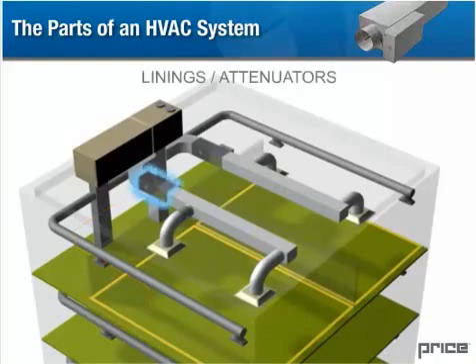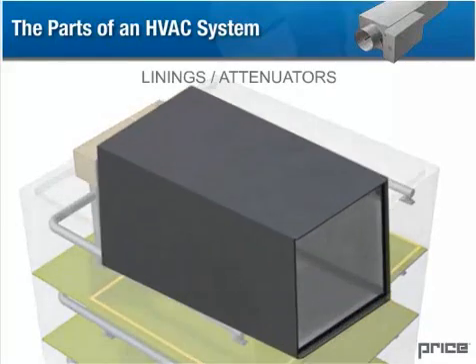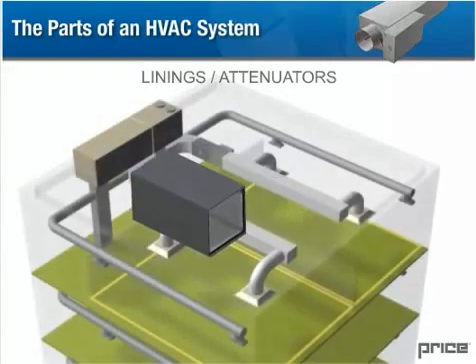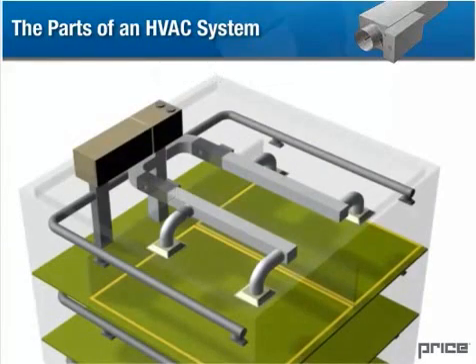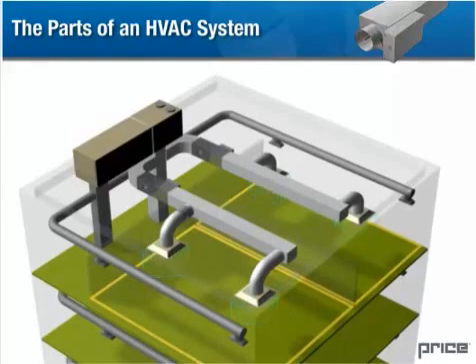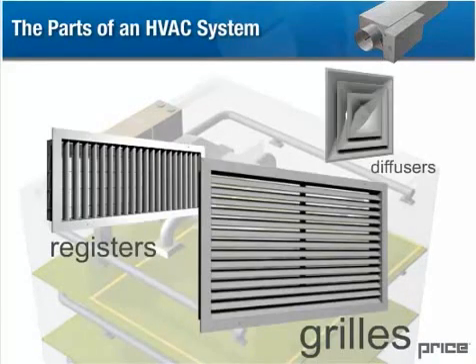Various types of linings are available to dampen noise within a duct. A short length of lined ductwork, called an attenuator, is often installed following the terminal unit to dampen discharge noise. Ultimately, the test of an HVAC system lies in its ability to deliver conditioned air to the occupant. Air from the ductwork enters the occupied space through grills, registers, or diffusers, often called GRDs.